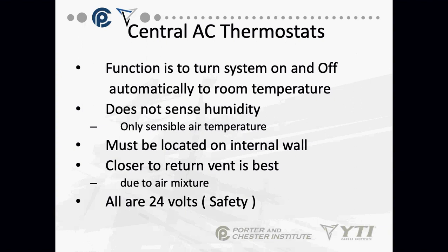Does anybody know why I don't ever put a thermostat on an external wall? It could be dangerous. Stays cold. Yeah, I'm going to pick up the outside air temperatures, okay? If my wall's cold, if the insulation isn't great, or if I have drafts, I don't want that to be hitting the back of the thermostat, okay? Because it's gonna either be too cold or too hot based on the wall temperature, okay? Walls are not solid, as those of you who just had design know about, okay?